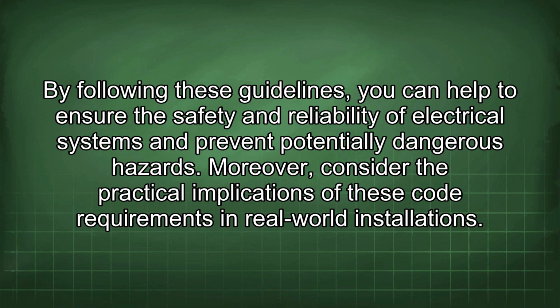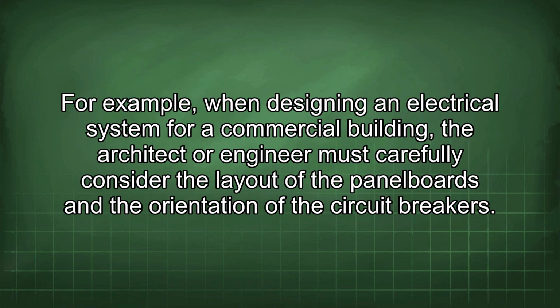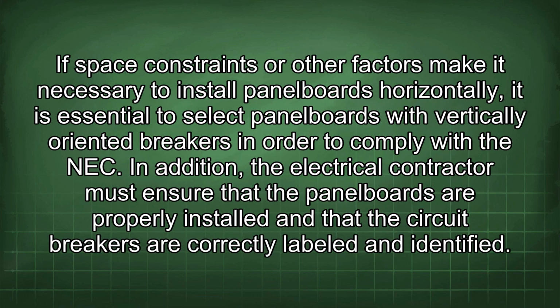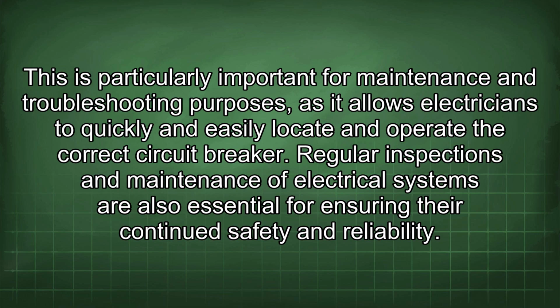hazards. Moreover, consider the practical implications of these code requirements in real-world installations. For example, when designing an electrical system for a commercial building, the architect or engineer must carefully consider the layout of the panel boards and the orientation of the circuit breakers. If space constraints or other factors make it necessary to install panel boards horizontally, it is essential to select panel boards with vertically oriented breakers in order to comply with the NEC. In addition, the electrical contractor must ensure that the panel boards are properly installed and that the circuit breakers are correctly labeled and identified. This is particularly important for maintenance and troubleshooting purposes, as it allows electricians to quickly and easily locate and operate the correct circuit breaker.